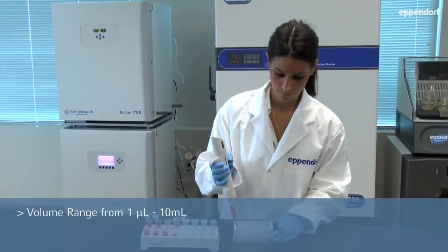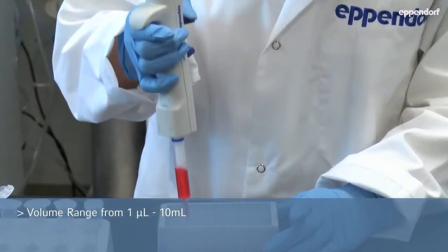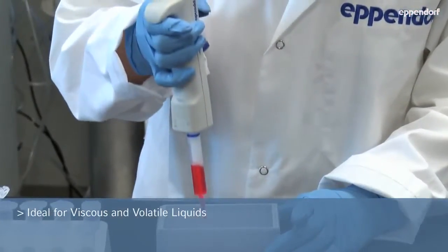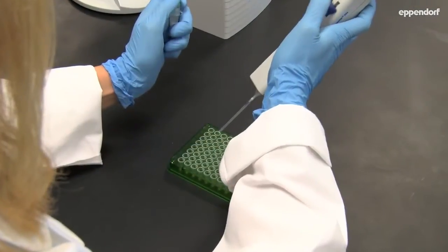Whether you're dispensing 1 microliter or 10 milliliters, the Multipette M4 delivers correct dispensing volumes you can count on, regardless of density, viscosity, or volatility of the liquid. Using positive displacement technology, the Multipette M4 delivers unmatched precision and accuracy when dispensing your sample.